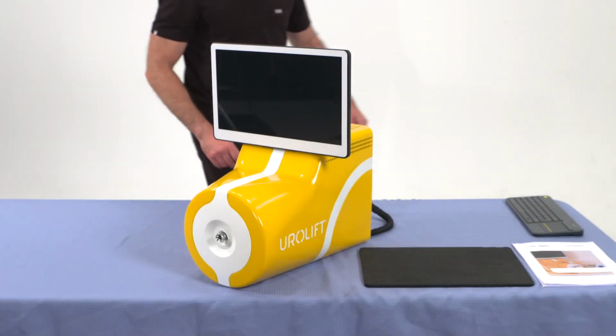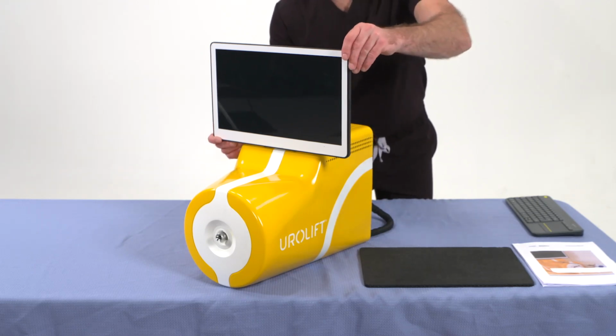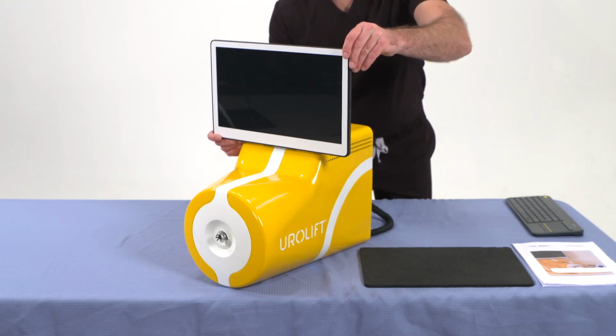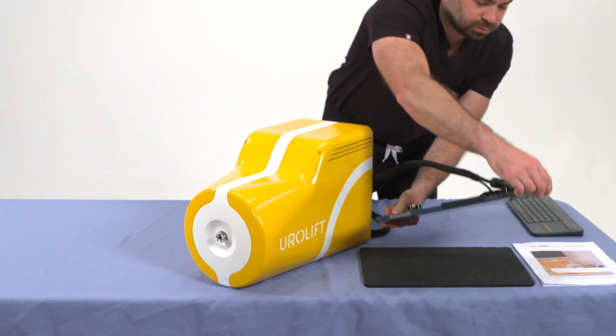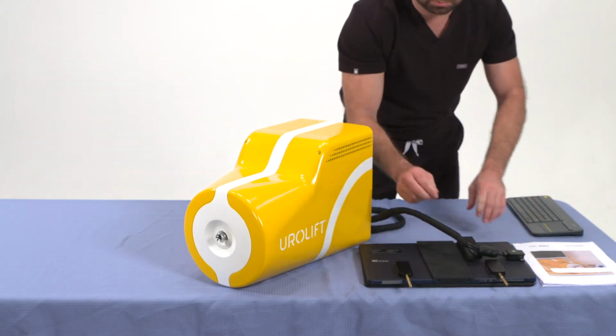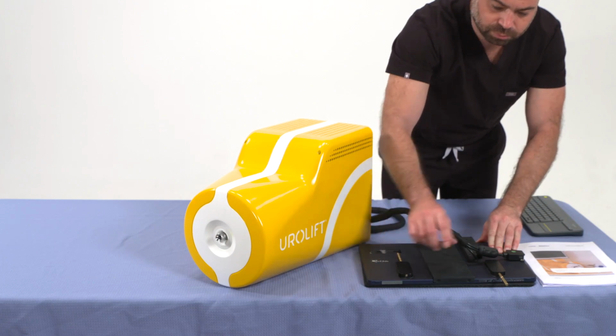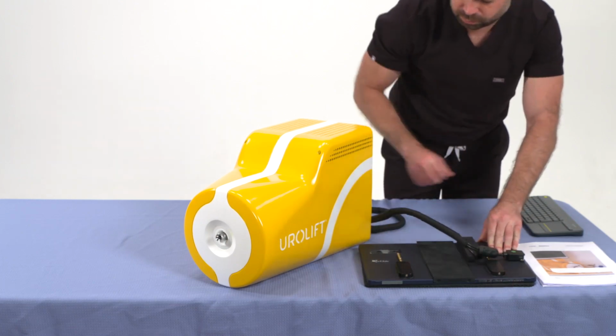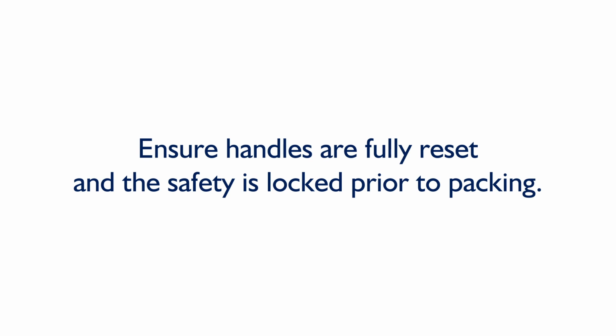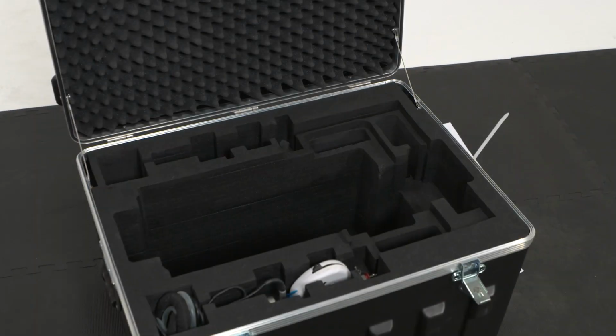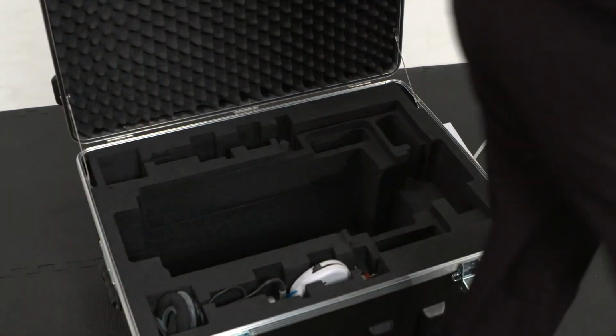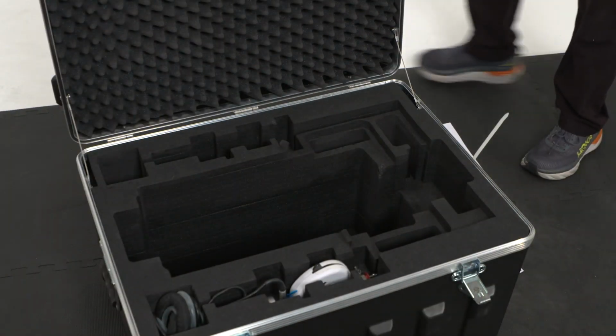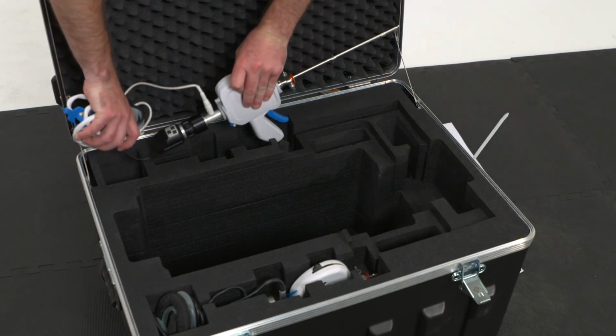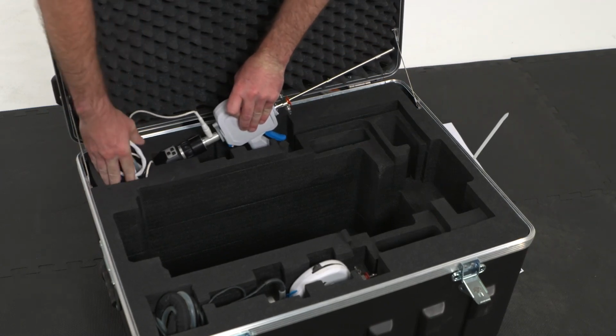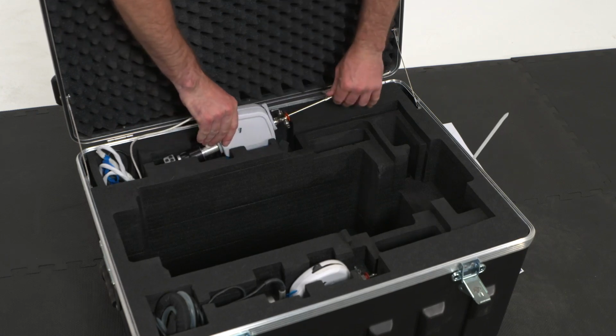To disassemble the simulator, grasp the monitor with both hands and lift it directly up to remove. Push the pins back into the monitor case and set the monitor aside in a safe place. Ensure handles are fully reset and the safety is locked prior to packing. Using two hands, place the UL400 and UL2 SIM handles in the slots at the front and back of the transport case. Remember to tuck the cord and tubing into the square cutouts in the corners to prevent damage.